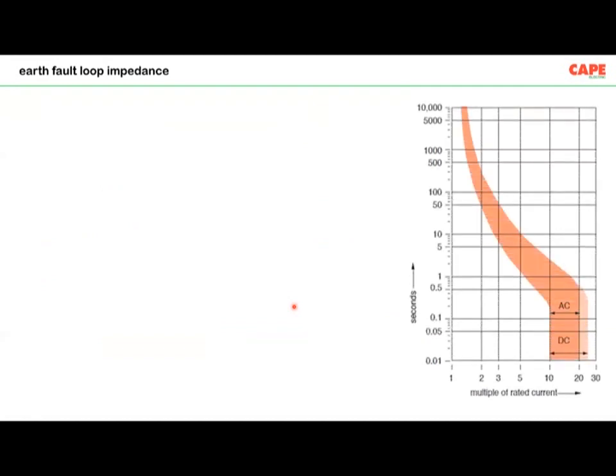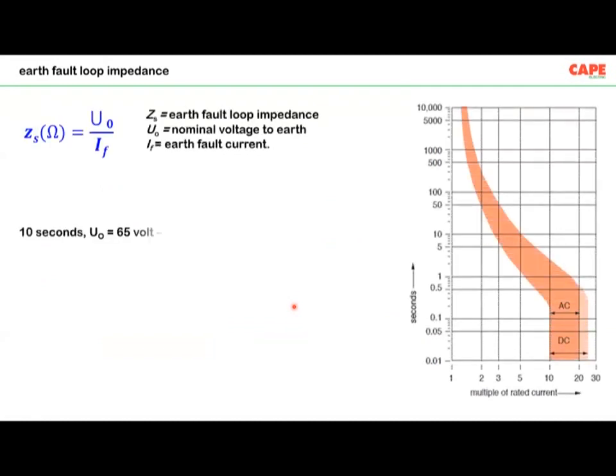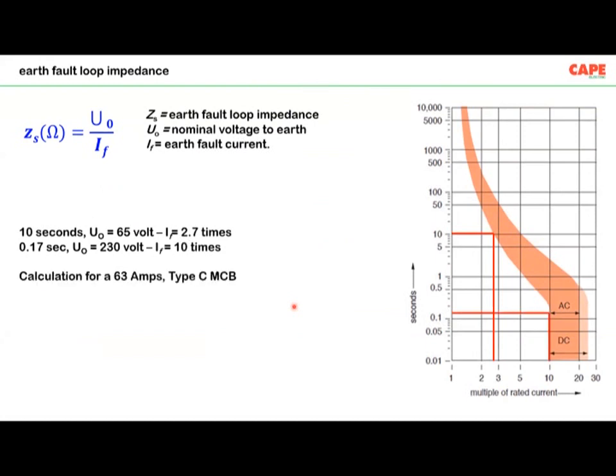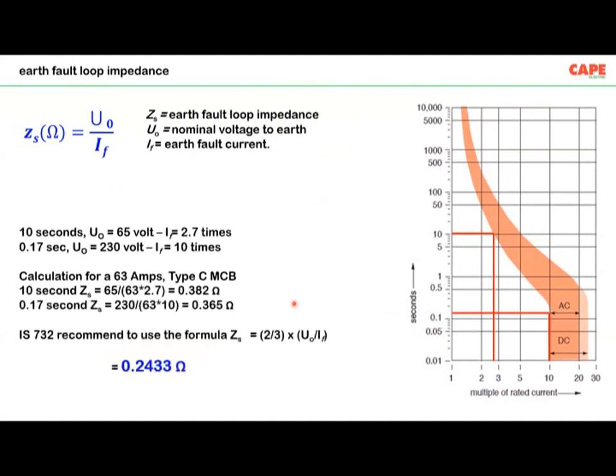Now, what is fault loop impedance? Basically, the calculations are given in the standard. I don't want to explain the calculations to you because most of you know them very well. The impedance of that particular circuit decides the amount of the fault current, which decides the disconnection time.